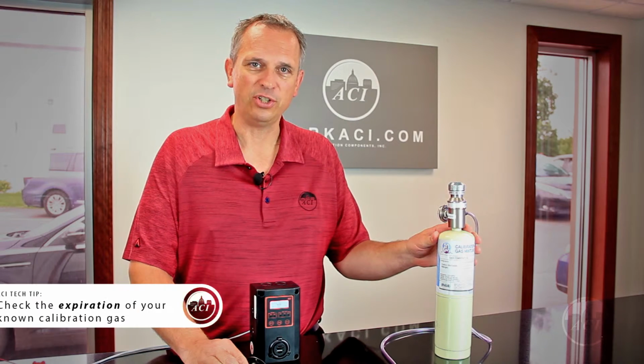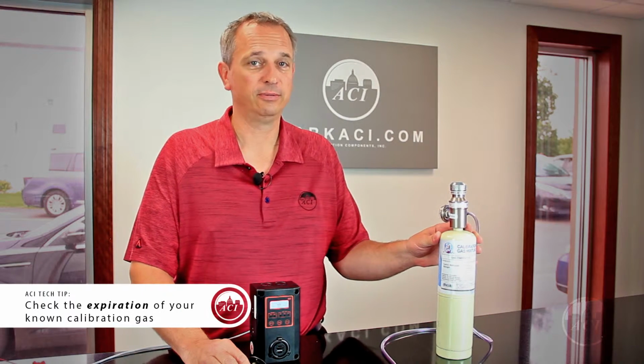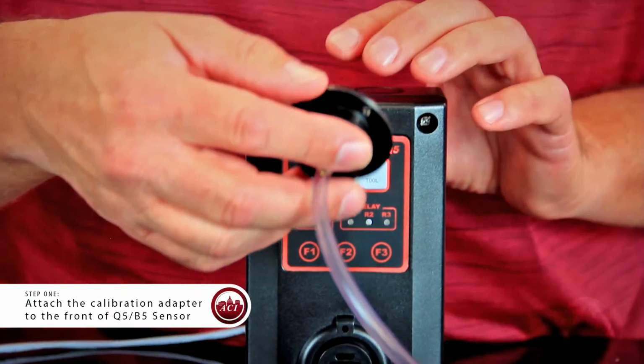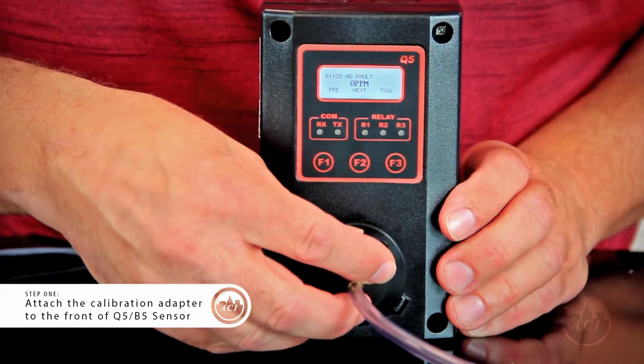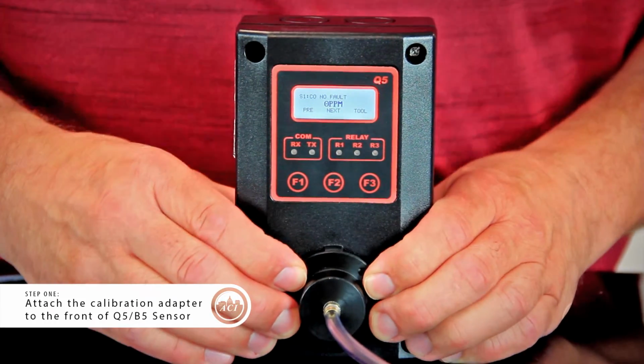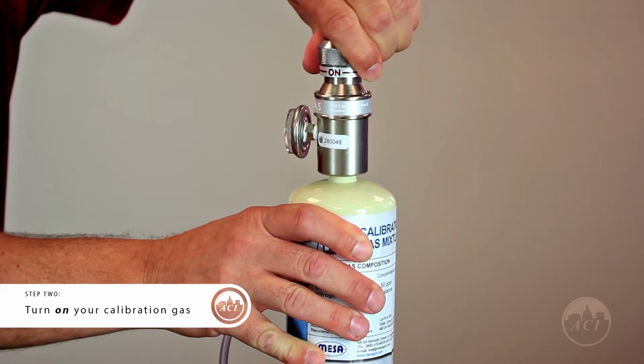All gas have an expiration date, so you want to make sure that the gas is still good. The sensor that I'm working with today is a Q5CO sensor, so I'm going to be using 50 parts per million as our bump gas. So what I'm going to do is I'm going to place the calibration adapter right over the sensor. And I'm going to turn on the gas now.